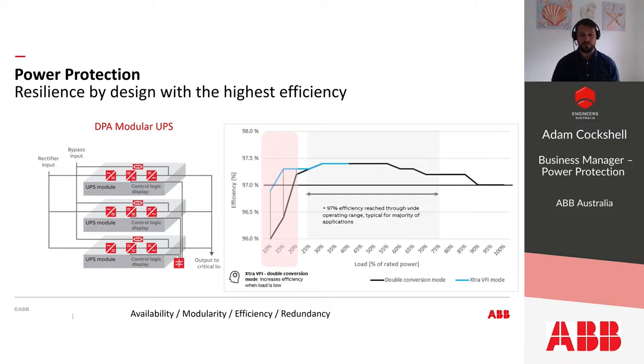Xtra VFI in our DPA architecture allows us to have the load supported, or N nominal, with a spare module, your +1, always maintained to your critical load in an active state, with all additional modules placed into a standby state, thus moving the load profile to a more efficient loading zone. The standby modules are ready and waiting, and if required, can come on due to a load increase. To ensure the modules age evenly, they rotate through an active and through a standby mode evenly throughout the life of the UPS.